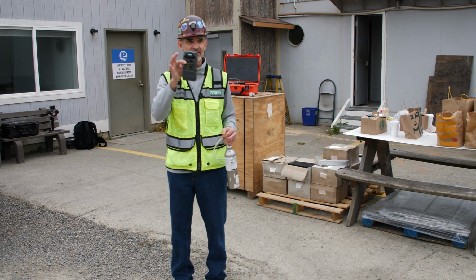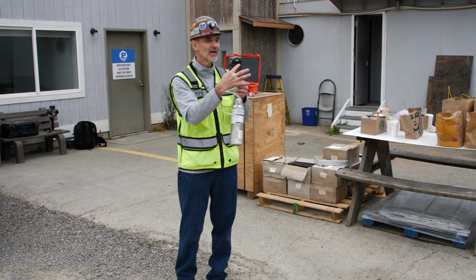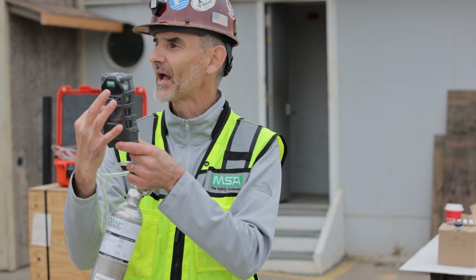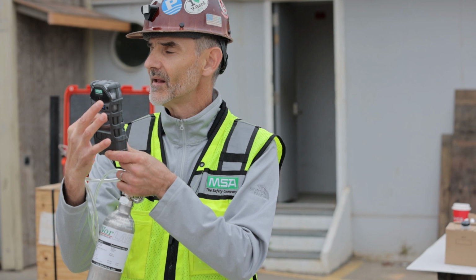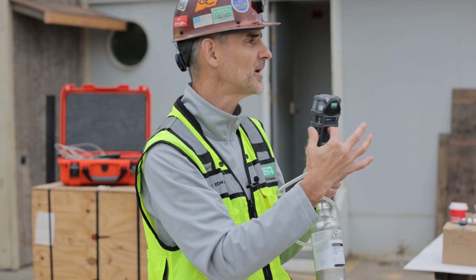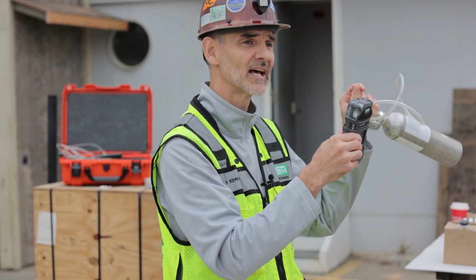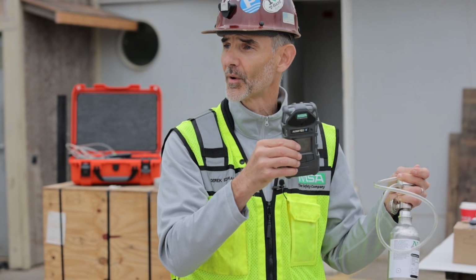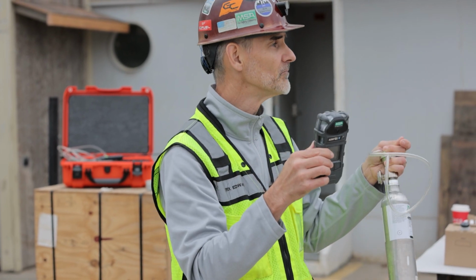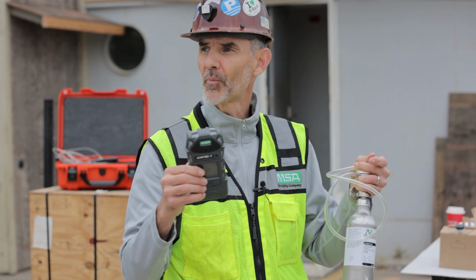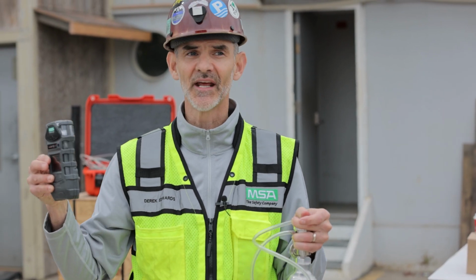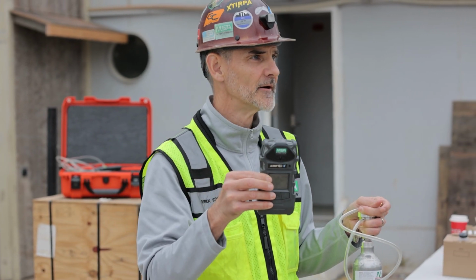Something else happened to this instrument. You can't see it, but there is a very small check mark at the top of this instrument. That check mark will only appear if a successful bump test or calibration has been done. So the training point, really important here: we only use an instrument that has a check mark.